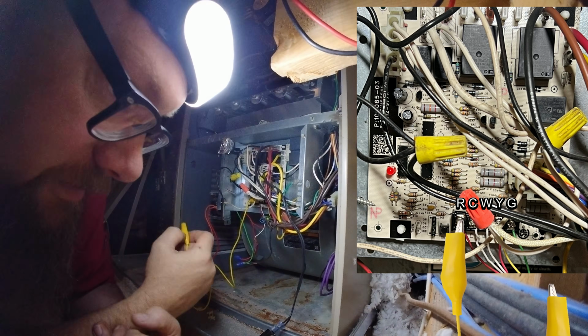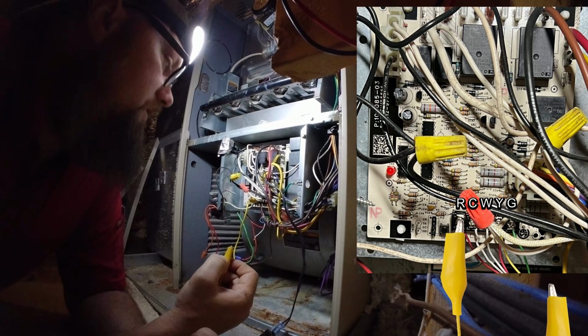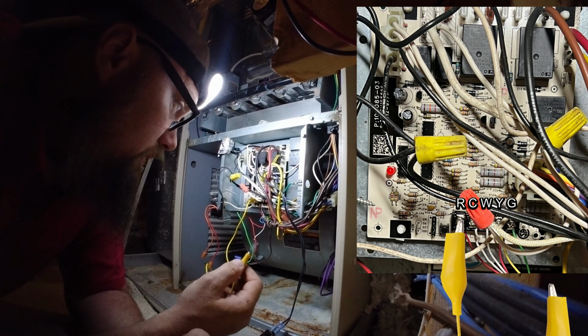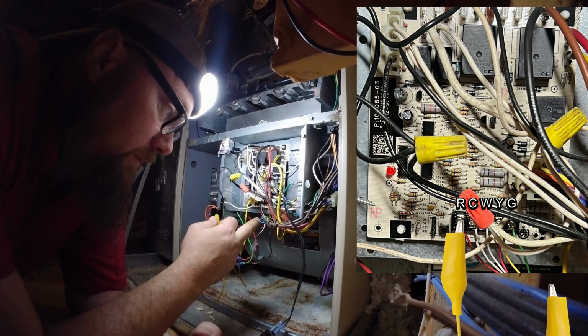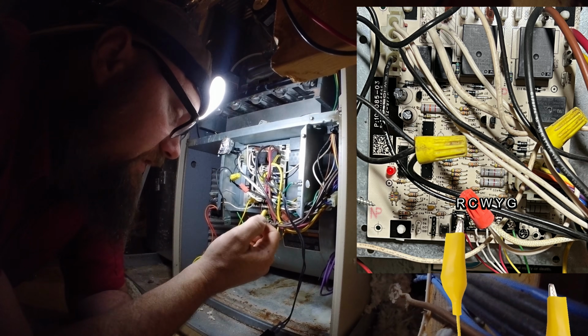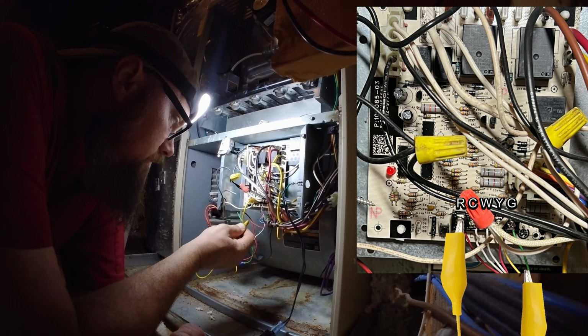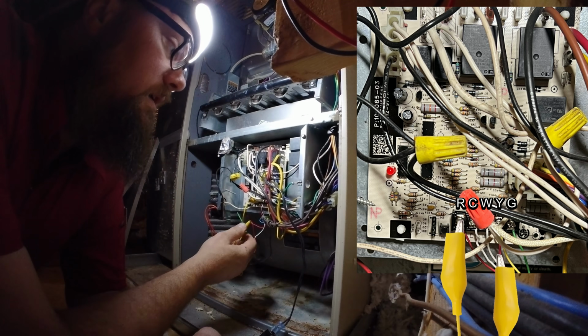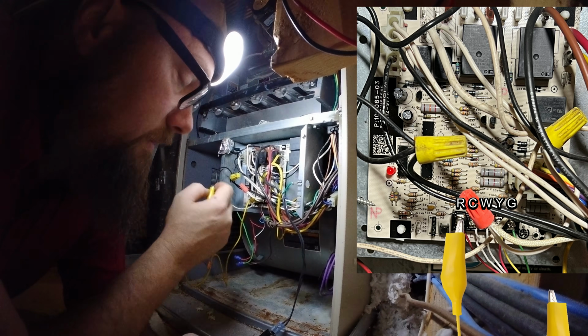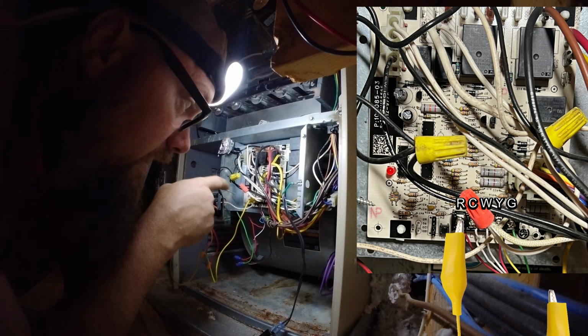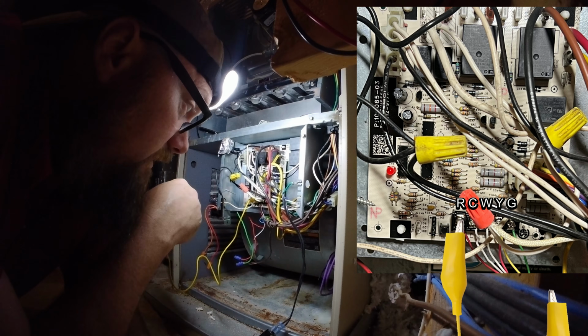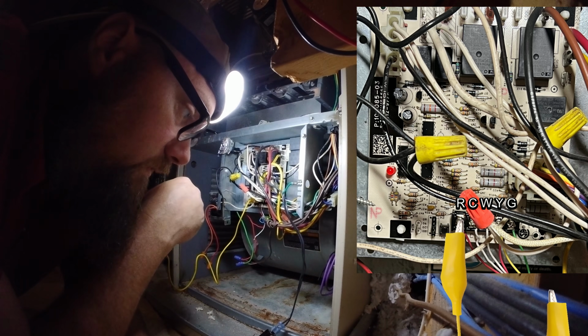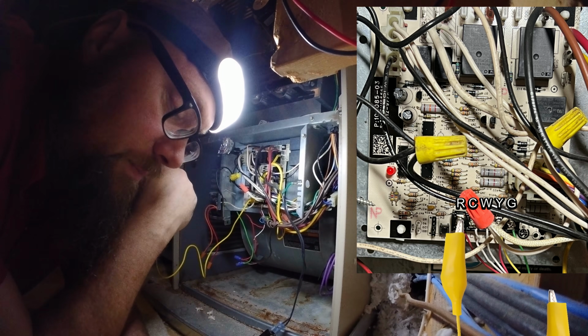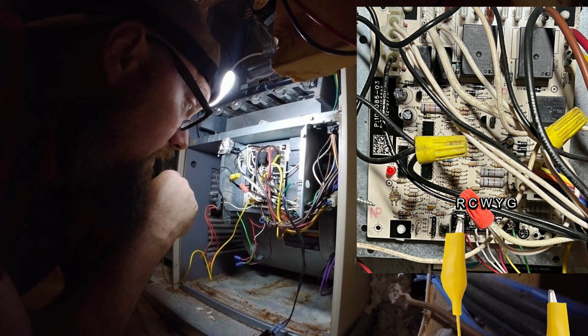Same thing there. Our zone board and everything is happy. Still have 24 volts. So we'll check between 24 volt hot and this red wire, which now just leads to the outdoor unit's control contactor. Alright, we'll quickly let go of that because just as soon as we contacted that wire, our red light went off. So that tells me it browned the system out for a second. Did not actually trip our 3 amp fuse, but that would lead me to thinking we've got an issue with the outdoor unit. So let's run out and take a look at that.